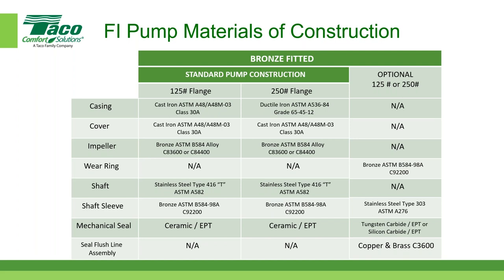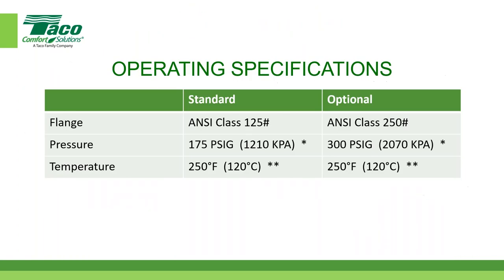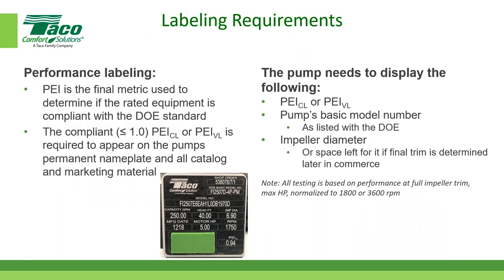We have a couple of quick questions, and I think we can answer a couple of them very quickly. One person wrote in, what is the difference between PEI-CL and PEI-VL? Someone asked earlier, what does PEI stand for? PEI stands for the pump energy index. The CL is for constant load, which means constant speed pumps, and VL means variable load or variable speed pumps. So the PEI VL value would imply that it has to be supplied with a variable frequency drive. Those are the distinctions between CL for constant load and VL for variable load.